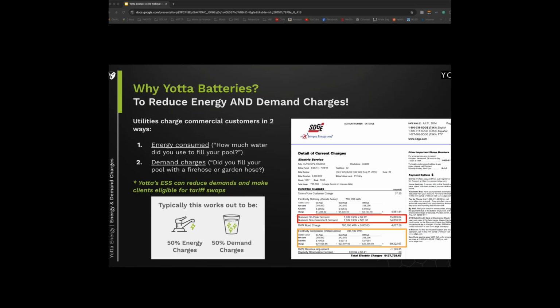When you add solar, you're offsetting that kilowatt hour usage, your energy charge, but you're not necessarily doing much, if anything at all, to the demand charge. So that's where the batteries come in. The batteries see when a demand spike happens and will discharge to lessen that spike, and the resulting effect will lower the bill for your client.